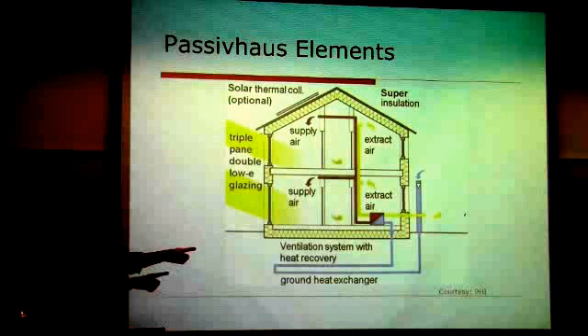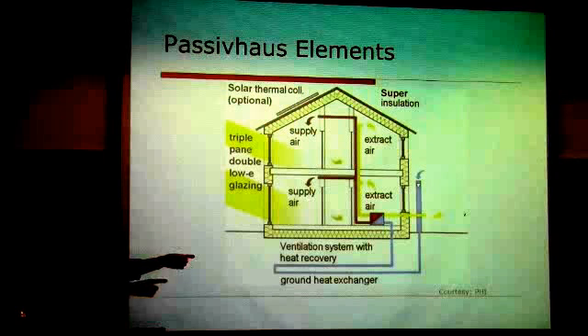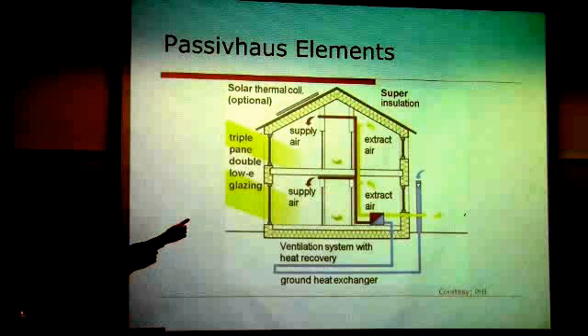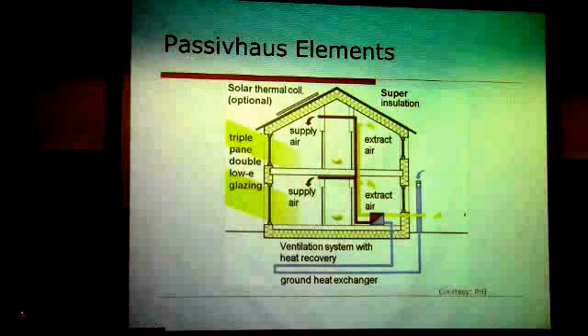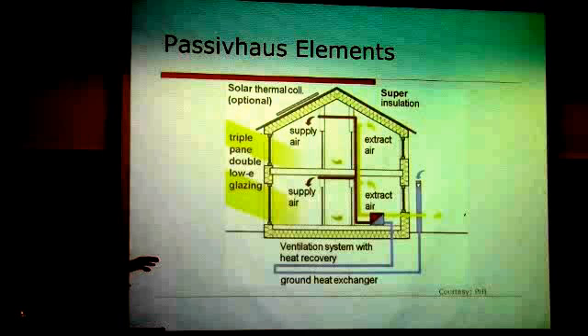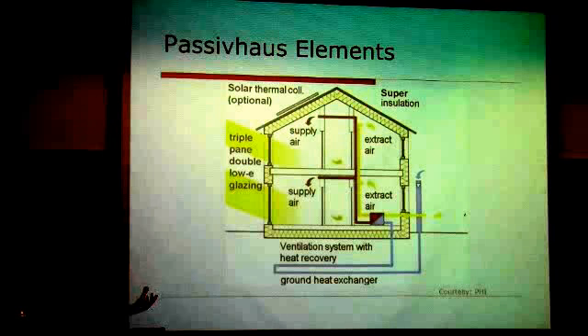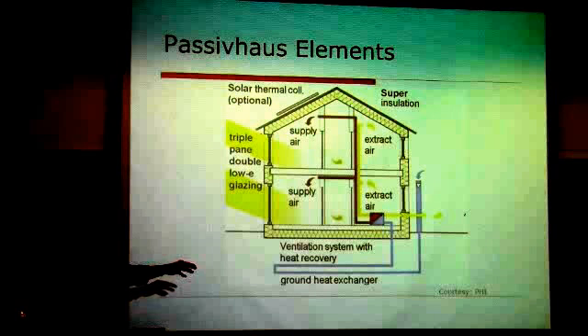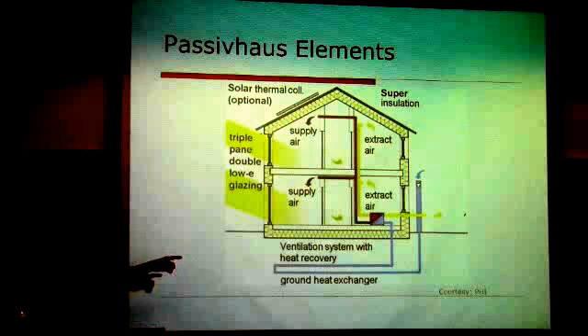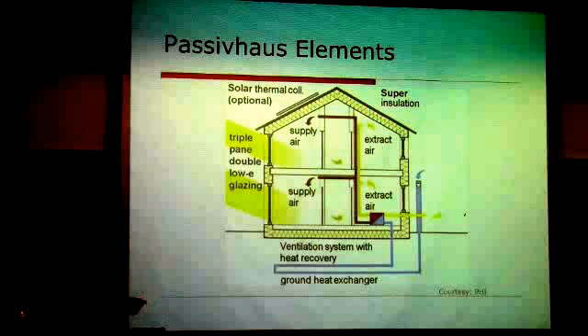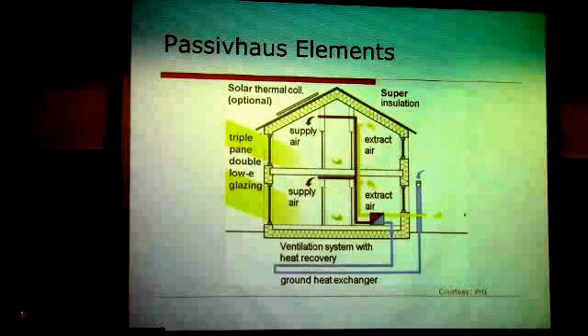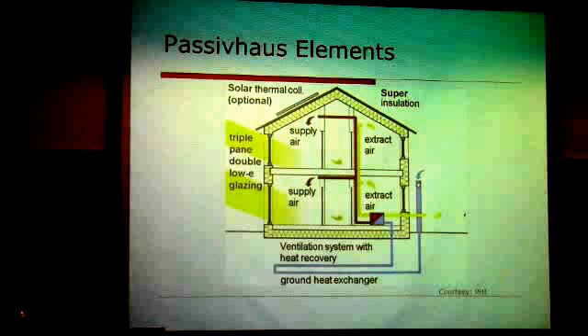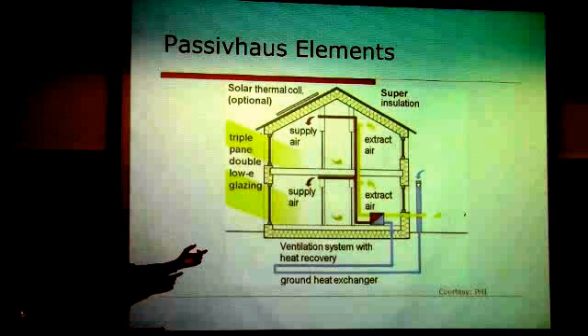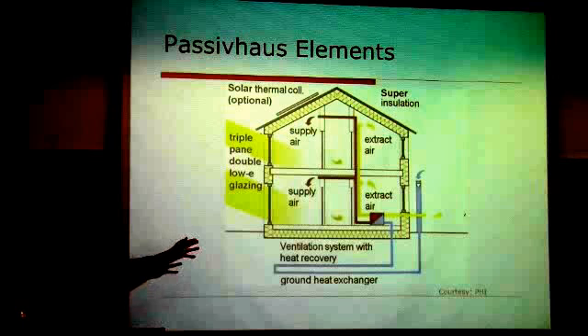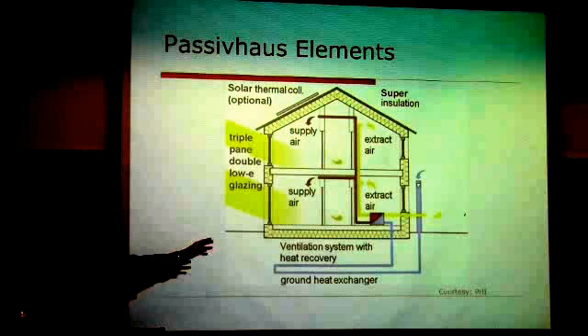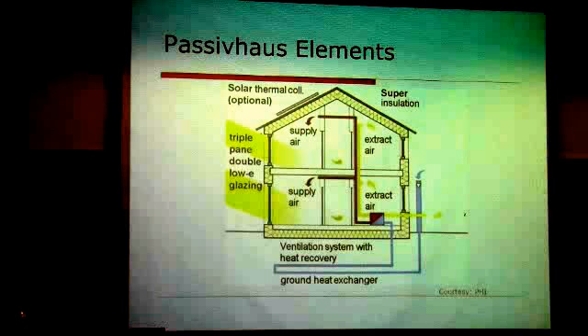But here it shows the inlet, say it's below freezing outside. It's trying to warm up the airflow through the ground first. In our systems, we just do a ground loop where the air never goes into an earth tube, because in certain moist climates, you might get condensation down there, and it's not the most hygienic, because you want your fresh air. So other systems like the one we have just run a loop, like a PEX loop in the ground, circulating water glycol through a hydronic coil, and the incoming air will go through the hydronic coil, and the pump for that coil will only run when it's necessary for heating. For example, if the air is negative 20 degrees outside, your ground temperature is usually 45 or so. It'll warm it up to near freezing, and then you don't have to do an electric preheater. People also use electric preheaters, but when you're trying to do near net zero, that uses a lot of energy.